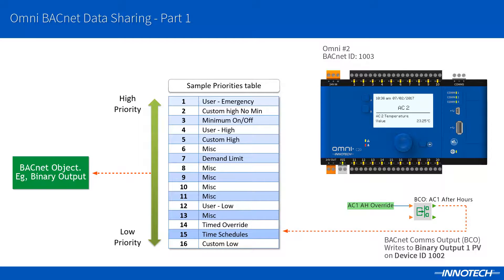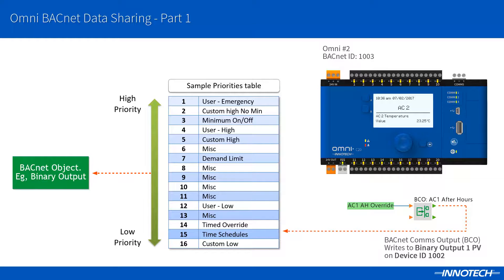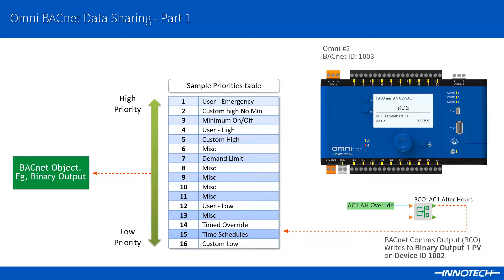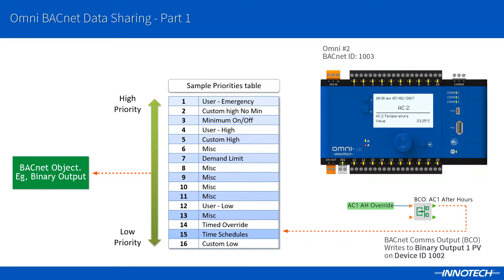The priority array works by allowing you to write a specific priority value to change the present value of the object. For example, if you have a binary output that is controlling a fan enable, a timed schedule may be controlling this at priority 15, which is a low priority. If a person wanted to press the after hours override for this unit when the schedule is off, the configuration would need to control this at a higher priority — in this case you could write the present value at priority 14. As this is a higher priority, it would override the lower priority of 15, thus enabling the fan control. Note that if the object's present value is controlled at priority 1, which is the highest priority, it cannot be overridden by a lower priority until this priority is relinquished or released, as no other priority below 1 will have any effect.